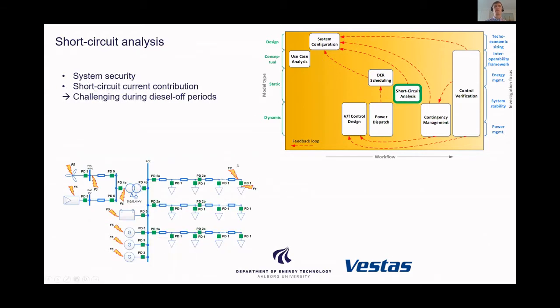Then a very important aspect already at the system configuration stage is to look into system security. And here we talk about the ability of the plant to handle short circuit faults, which requires a comprehensive analysis of all the possible faults that could happen in such an off-grid system. The most challenging cases are actually when the synchronous generators are not in operation, because then you have only the inverter-based units contributing to the short circuit fault, which might be tricky.